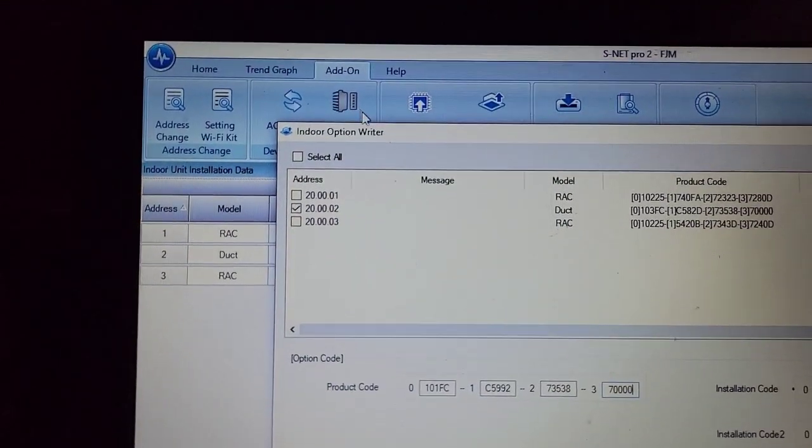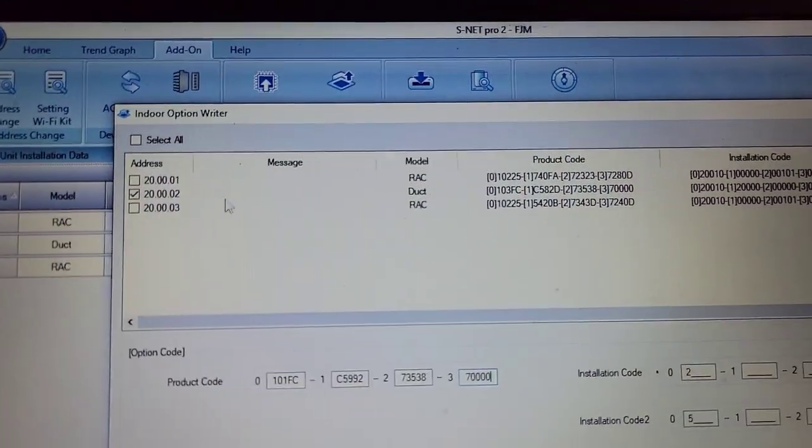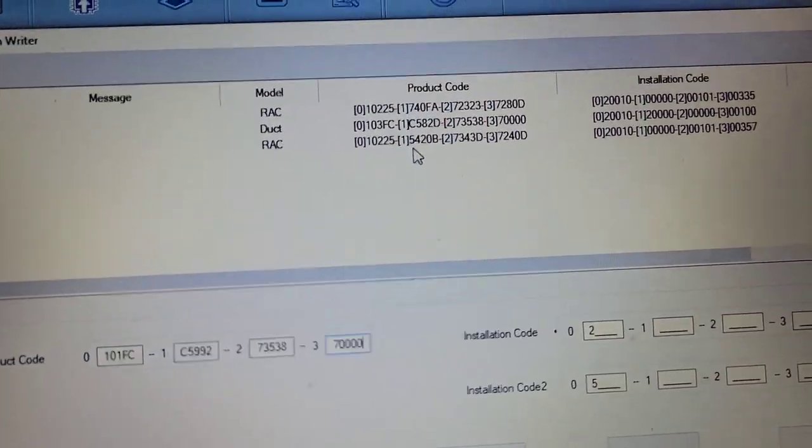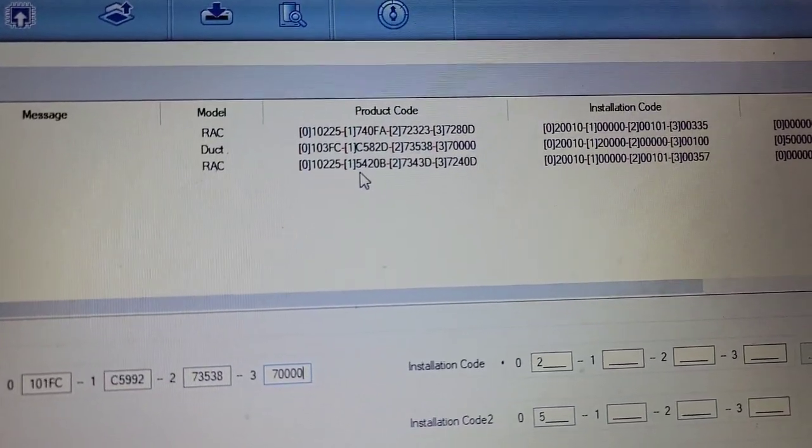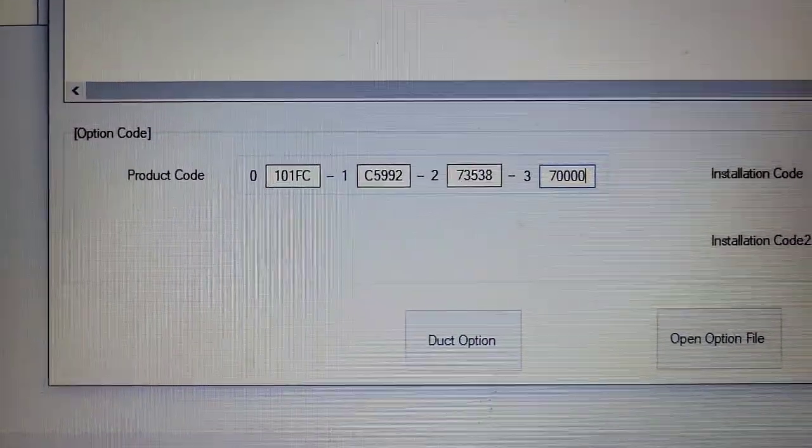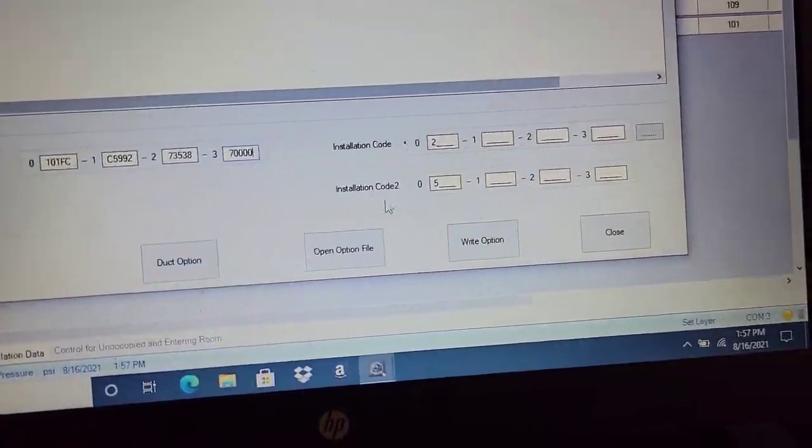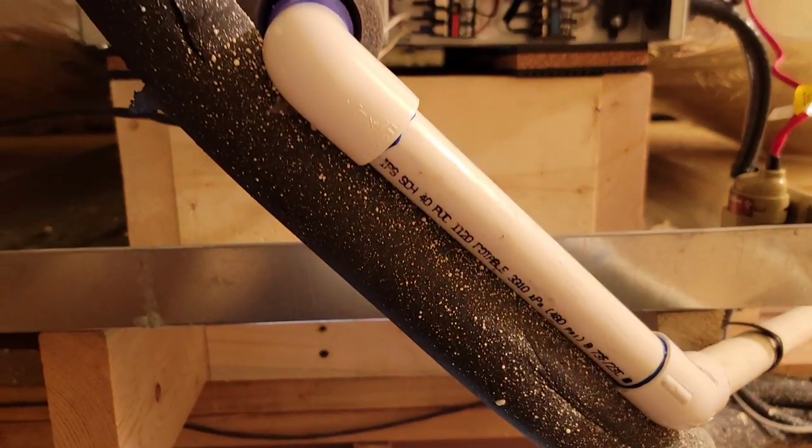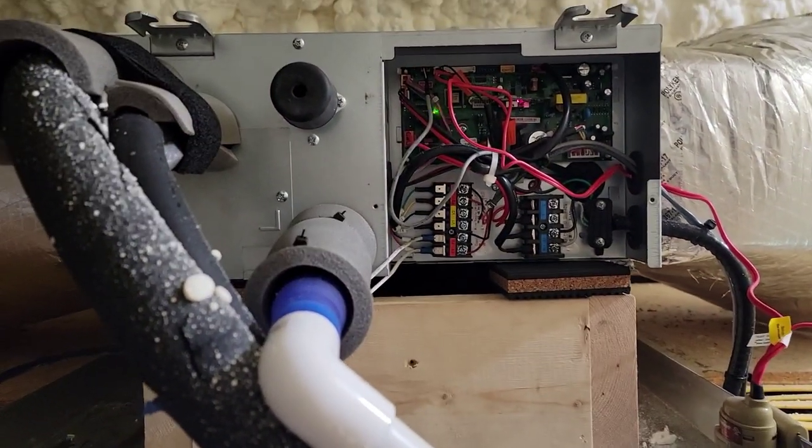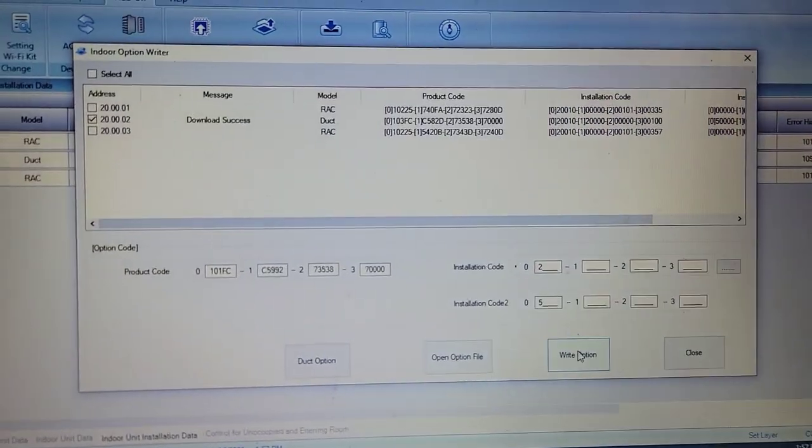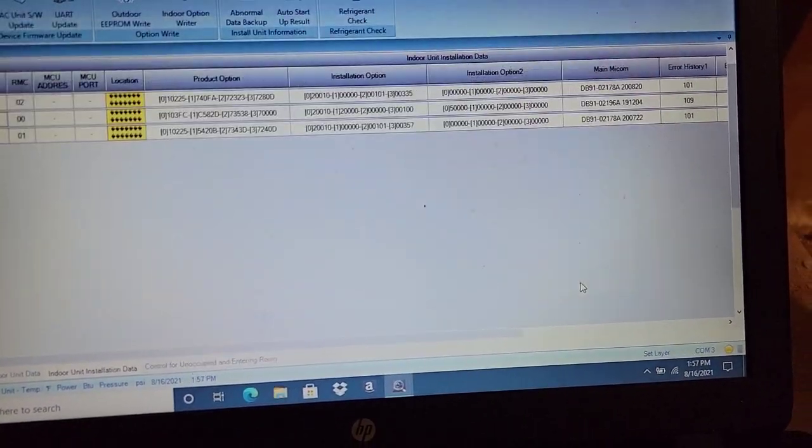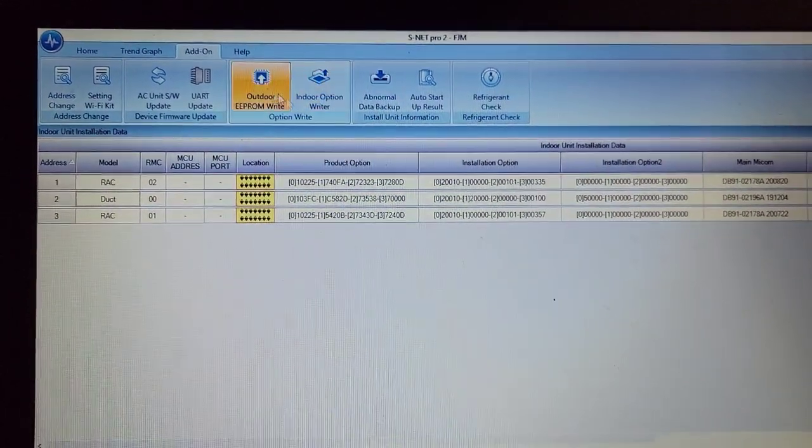This is the sound of the unit idling right now. Then I'm going to notice the sound when I write the option, how I do it. Go to add on, go to write option, specify the indoor unit. I'm going to add the code for the ducted. This is the code right now, 0103FC-1C582D-273538-370000. This is the code I have put in. And then I'm going to go over here and push write option. I think I'm changing the speed from 0.08 to 0.16. Just wrote that option there, download success.